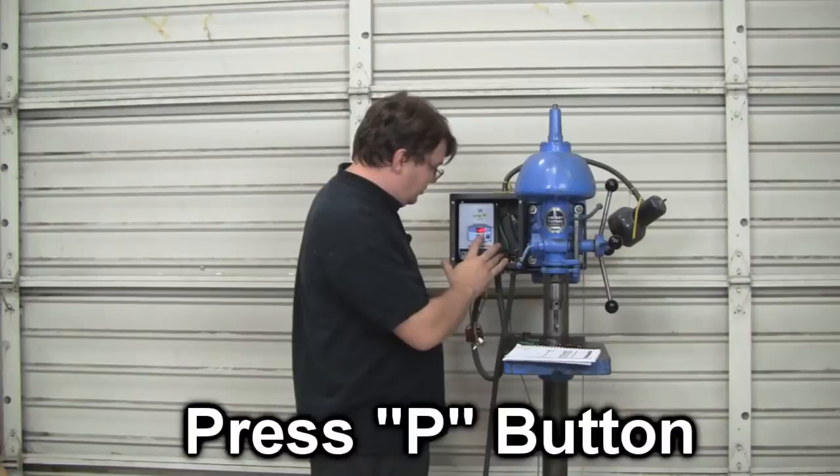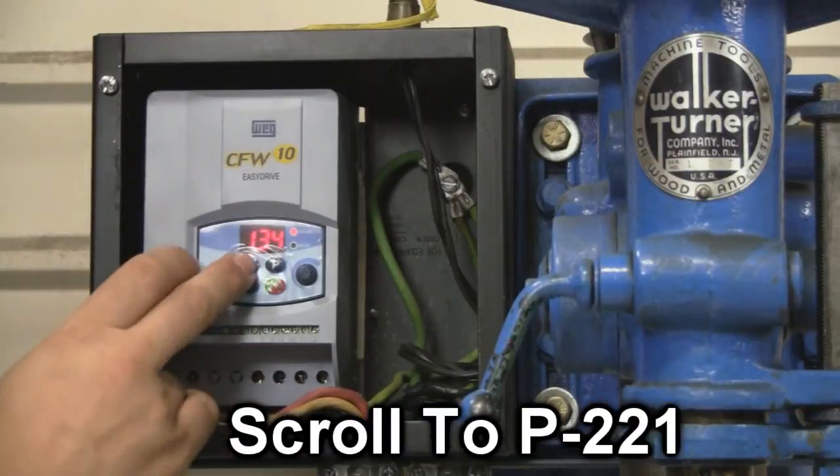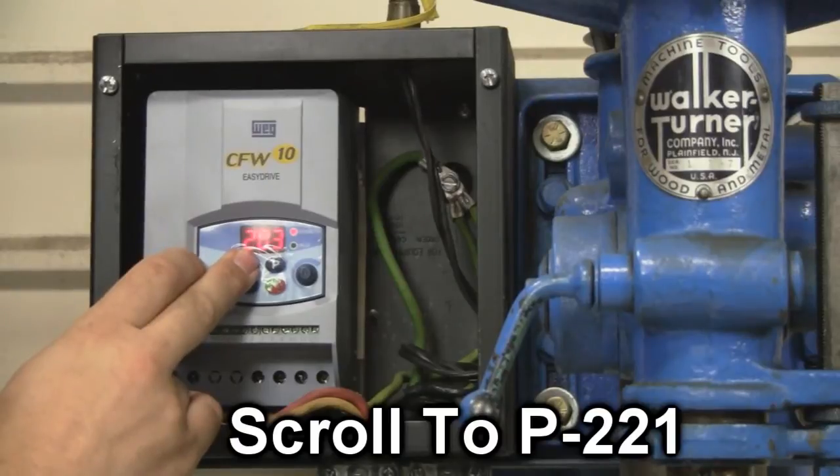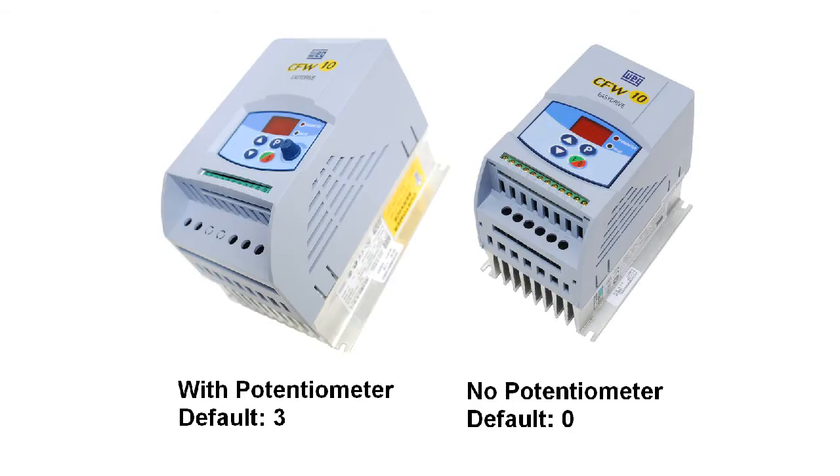I need to go into the menu by pressing P, and I need to scroll to P221, like I said, and I need to go ahead and change this. The default is 3 for this particular version. It will be 0 for standard style inverters.